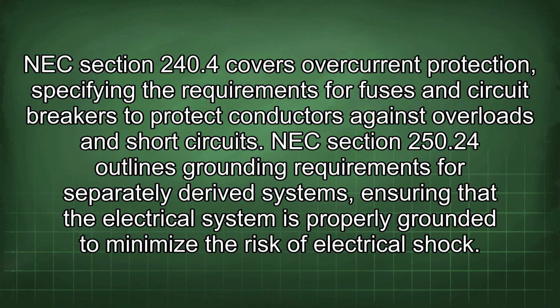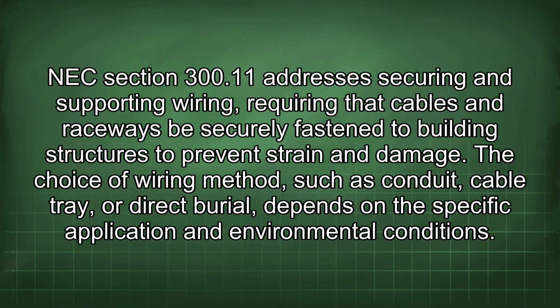NEC Section 240.4 covers overcurrent protection, specifying the requirements for fuses and circuit breakers to protect conductors against overloads and short circuits. NEC Section 250.24 outlines grounding requirements for separately derived systems, ensuring that the electrical system is properly grounded to minimize the risk of electrical shock. NEC Section 300.11 addresses securing and supporting wiring, requiring that cables and raceways be securely fastened to building structures to prevent strain and damage. The choice of wiring method, such as conduit, cable tray, or direct burial, depends on the specific application and environmental conditions.